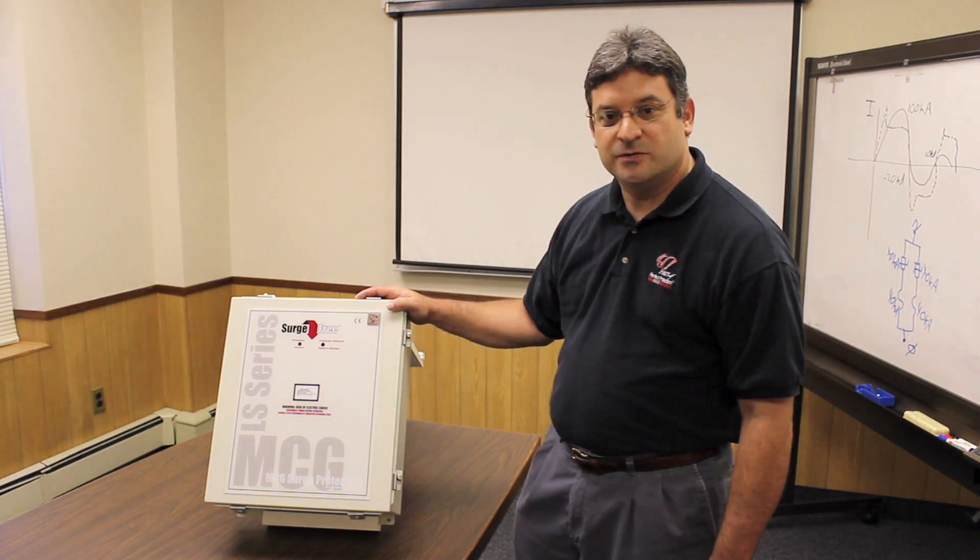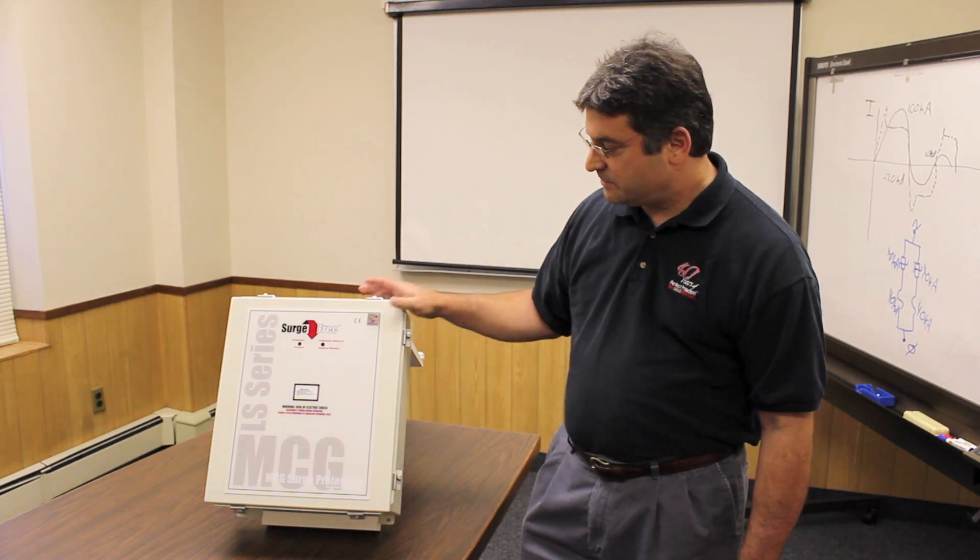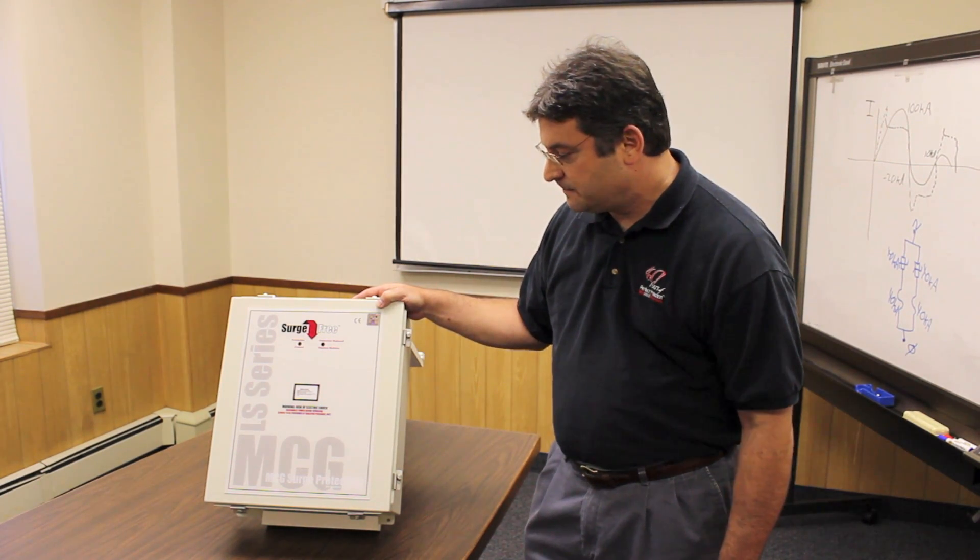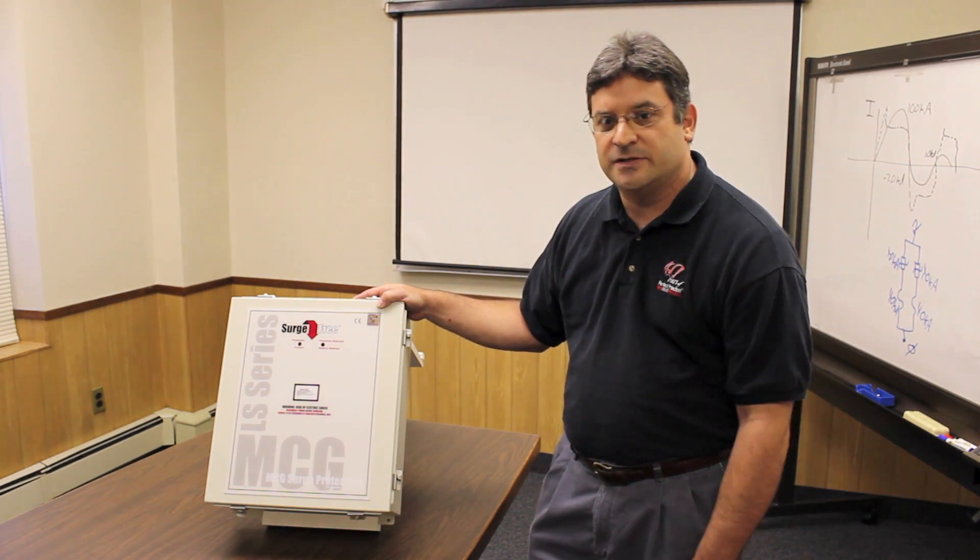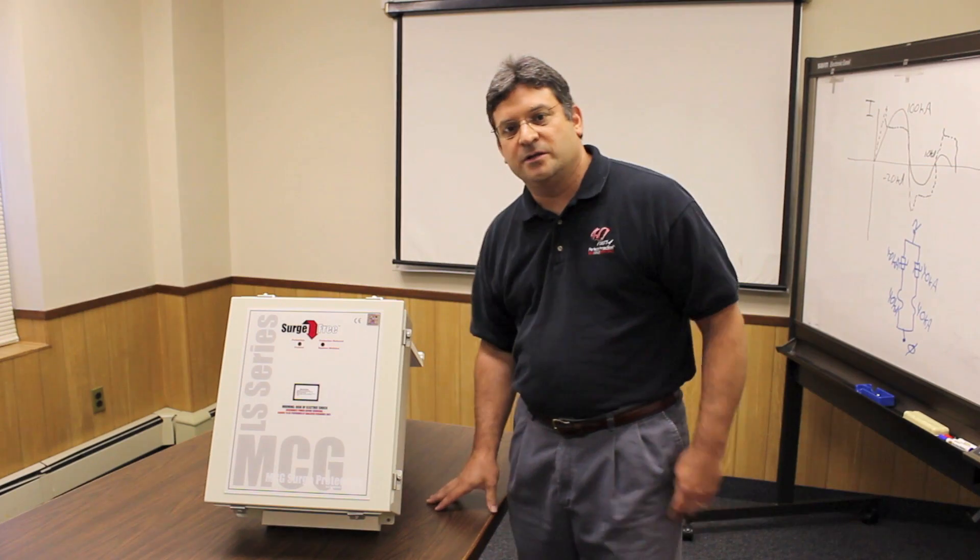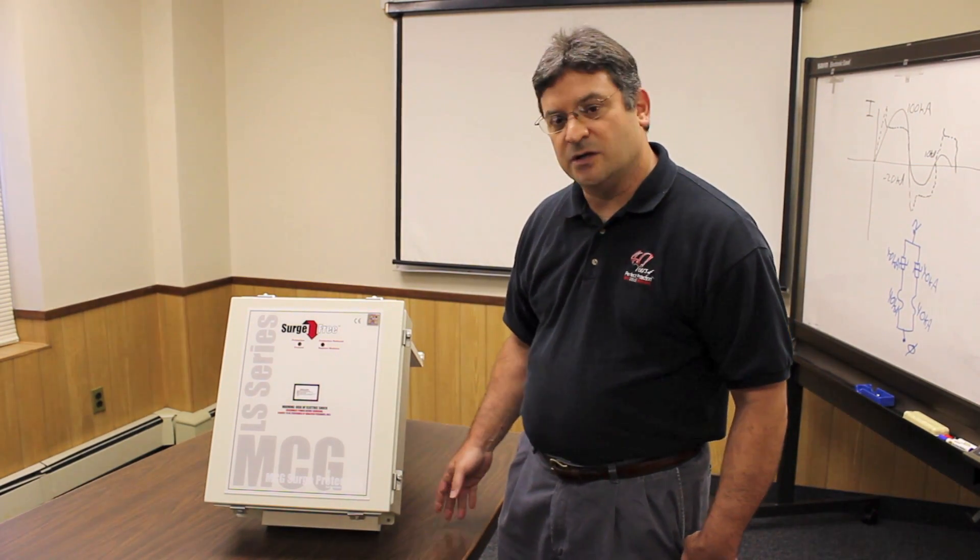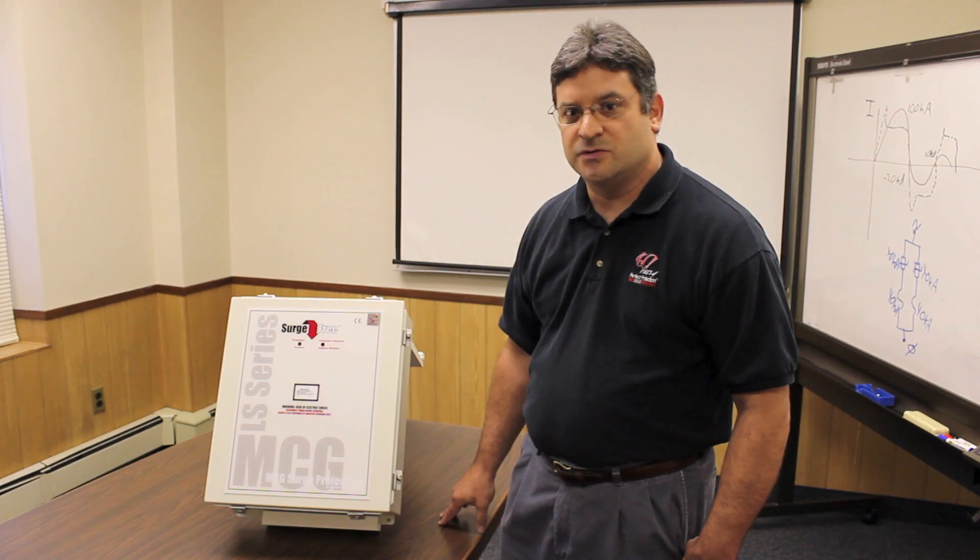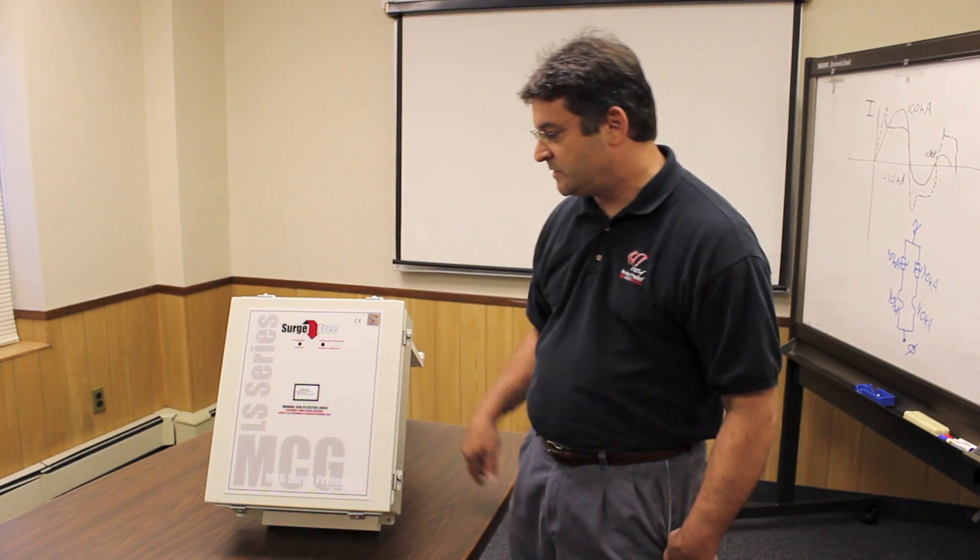Today I want to introduce you to our LS series of surge protection products. This model here is a 560 LS, but we also have the 300 LS, the 200 LS, and the 120 LS. The model name corresponds to the I peak per phase. The 120 is 120,000 amps per phase, the 200 is 200,000 amps, the 300 is 300,000 amps, and the 560 is 560,000 amps per phase.